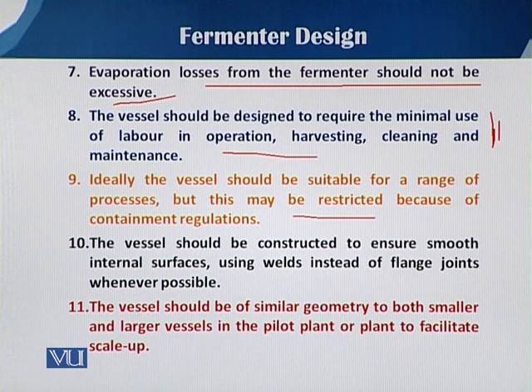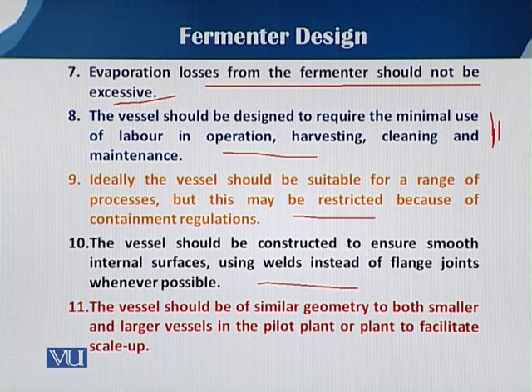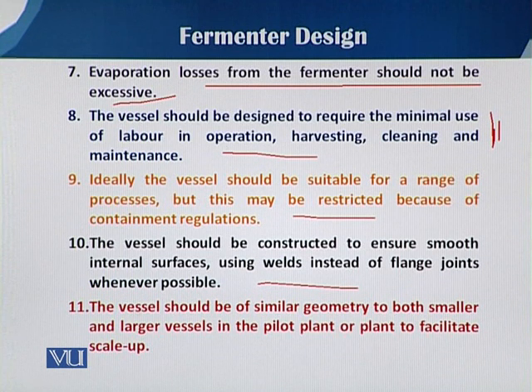The tenth requirement is very critical: the vessel should be constructed to ensure smooth internal surfaces because organisms have to grow inside. If there are minor pores or the surface is not smooth, there is a chance of contamination and we cannot clean the internal surface of the fermenter properly. We should avoid fermenters which have flange joints.